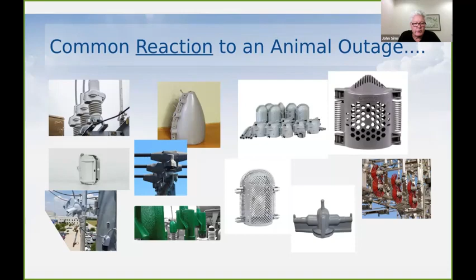This creates many other questions as well. Which one am I supposed to use? Where? It's got to be the right size, the right voltage rating. How many times am I going to have to take it off and do thermography? Is there standard maintenance for weather, voltage, or UV aging? Is it actually going to stop the animals I'm concerned about, or just squirrels? All of those are relevant questions when looking at a standard animal guard.